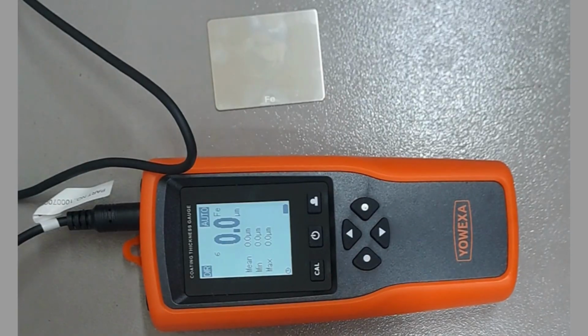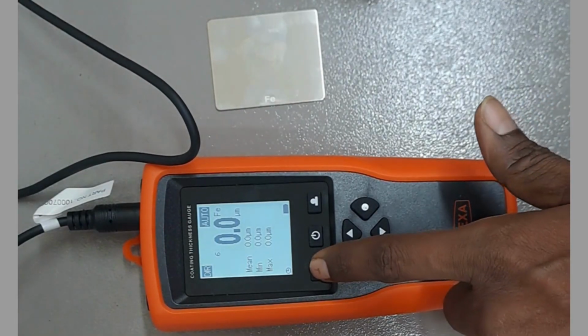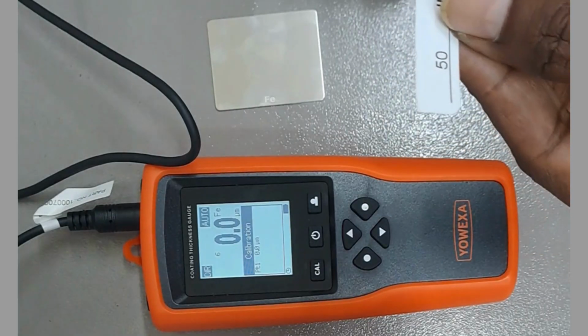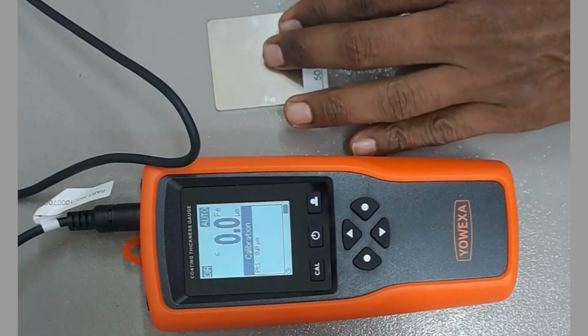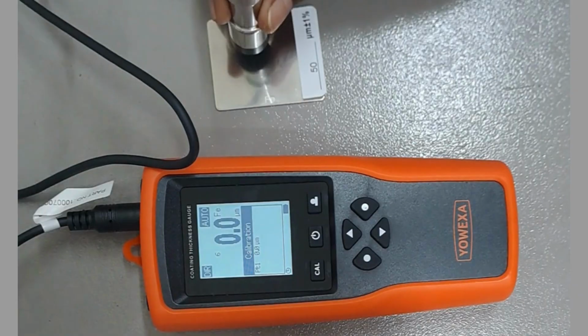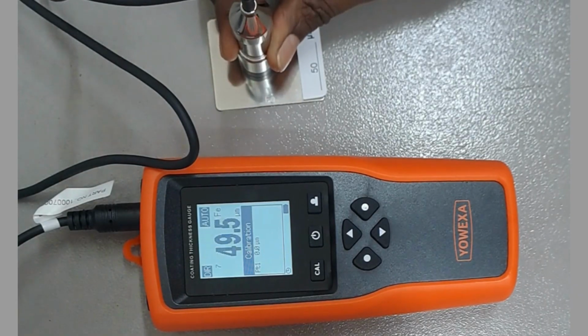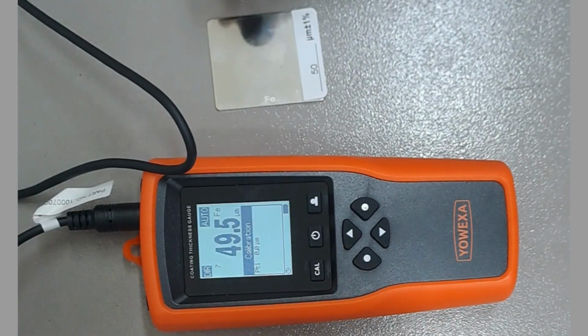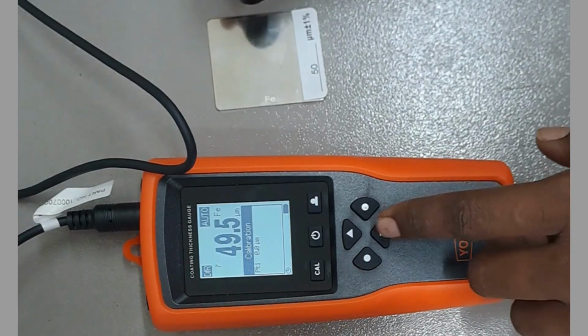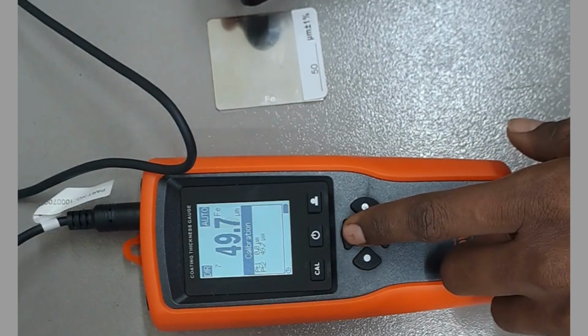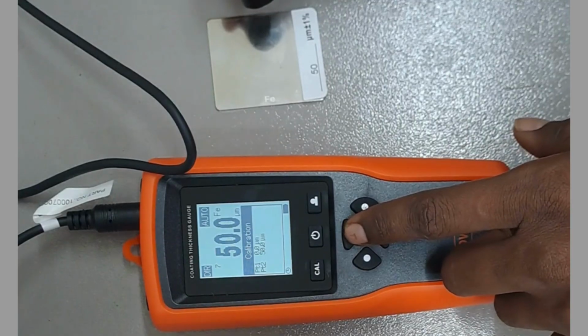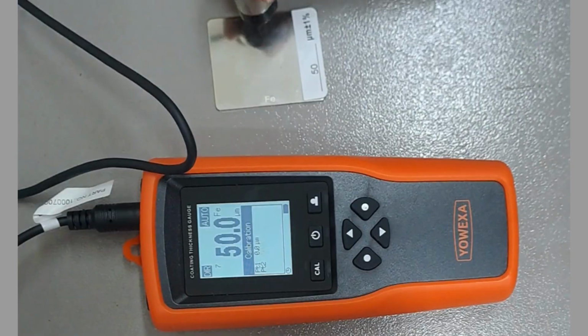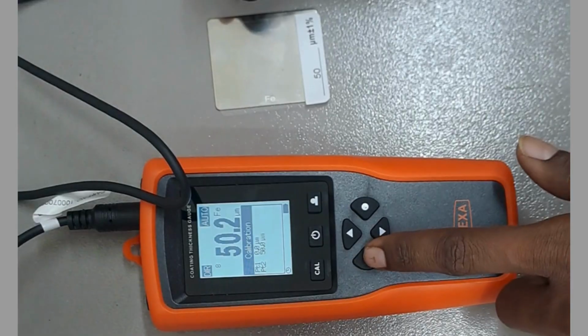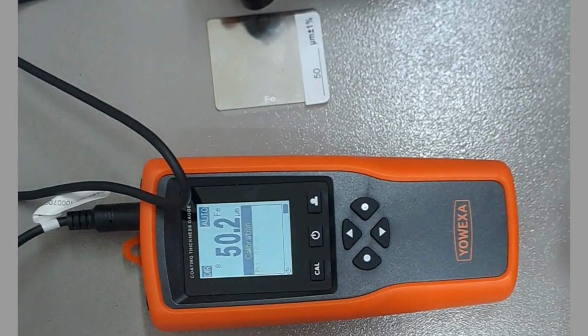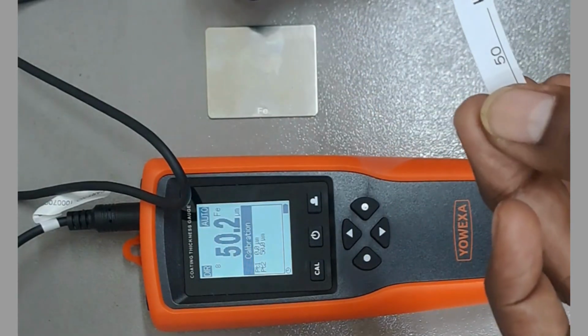Now we will do the calibration of the foils. So press the cal button once. We will do for 50 micron. Keep the foil over the base plate. Now place the probe on the foil and raise it after 1 beep. Okay, it's 49.5, but now we have to adjust to 50 micron. So press this button until the display shows 50 micron. Okay, so now it's 50 micron. Then press this button to confirm the second point calibration. So now the second point calibration for 50 micron is over.